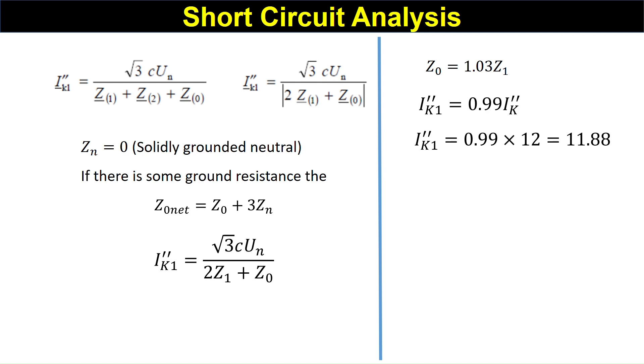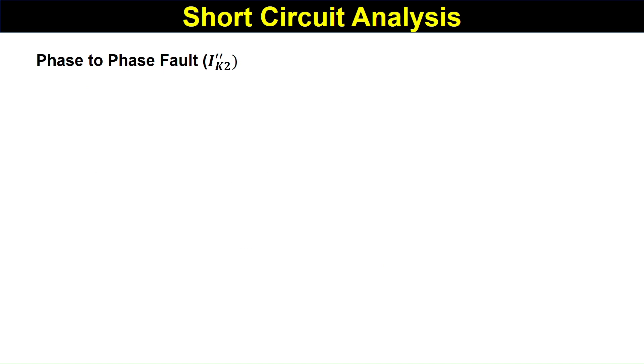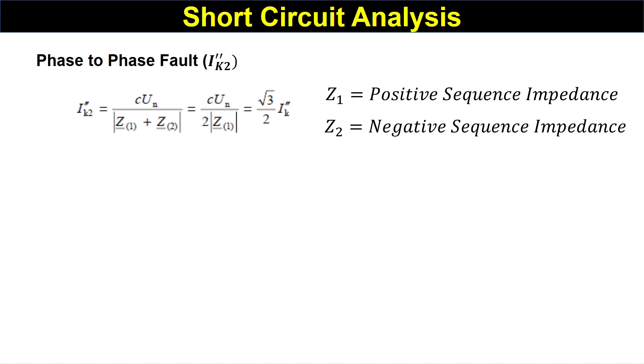Now we can calculate the line-to-line fault current, I_k2 double dash. I_k2 double dash equals c_un divided by Z1 plus Z2. Here the zero sequence impedance plays no role; only positive and negative sequence impedances are involved. Since Z1 equals Z2, it equals c_un divided by twice Z1, which becomes root three divided by two times I_k double dash. Putting in the value, I_k2 double dash equals root three divided by two times 12, which gives 10.39 kiloamperes.